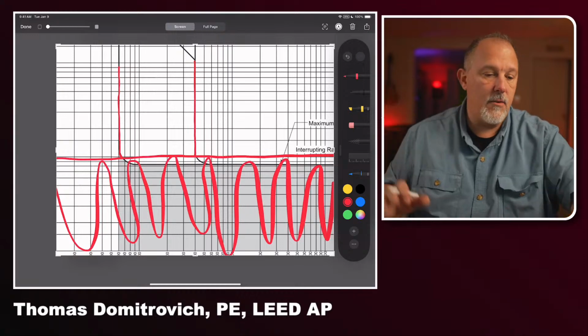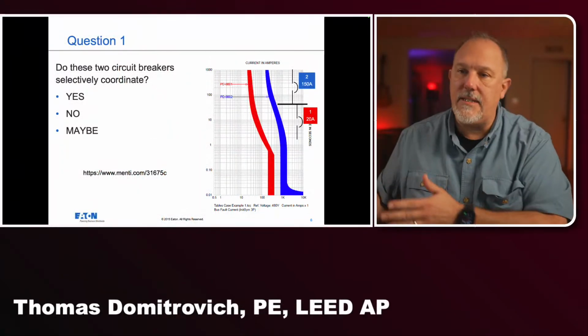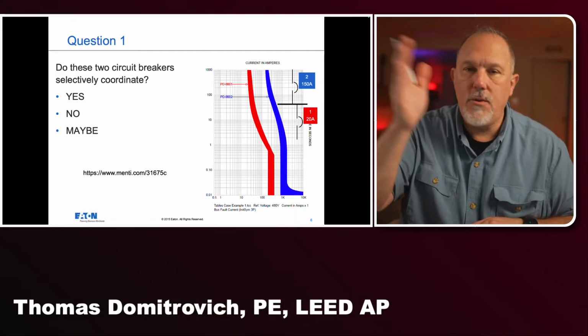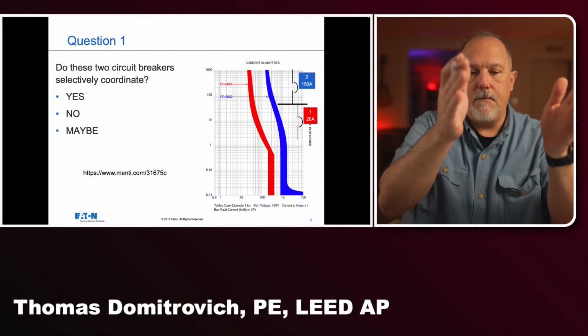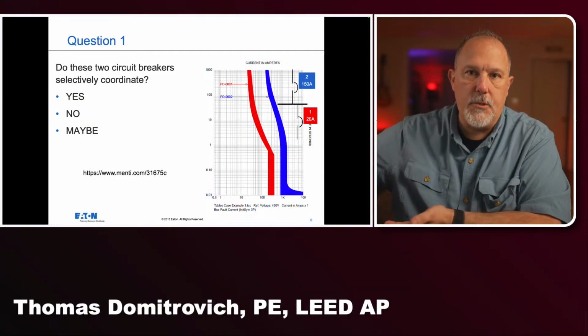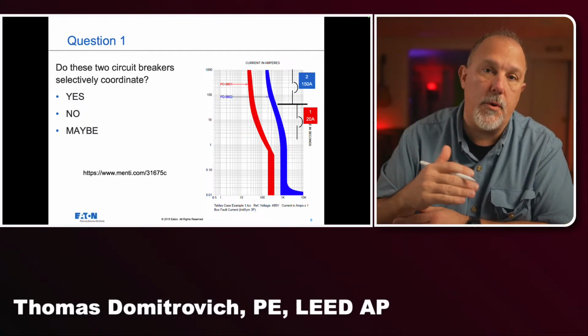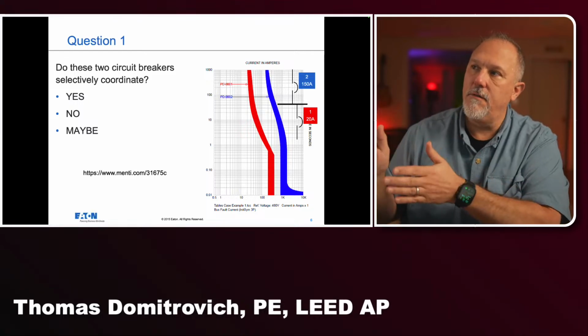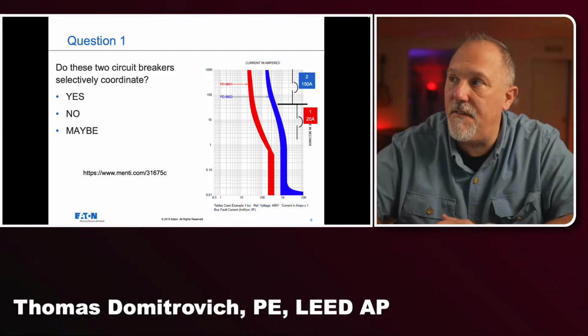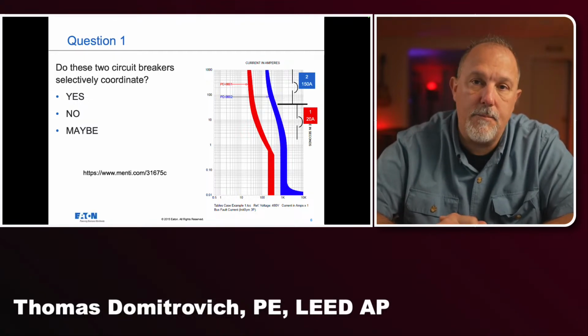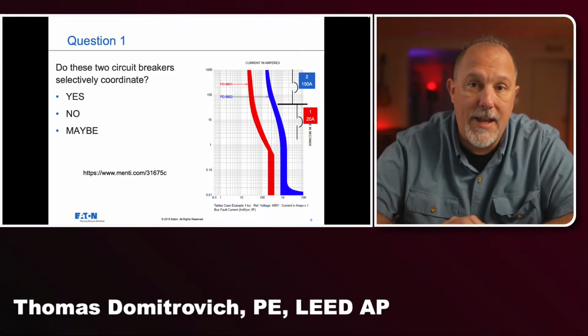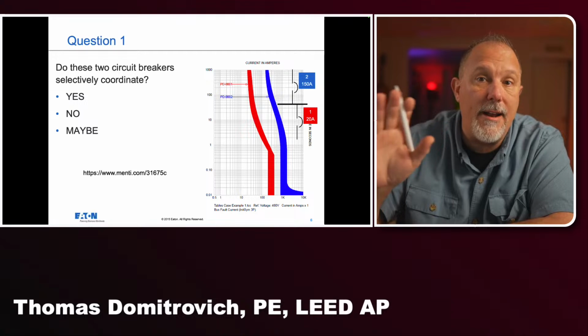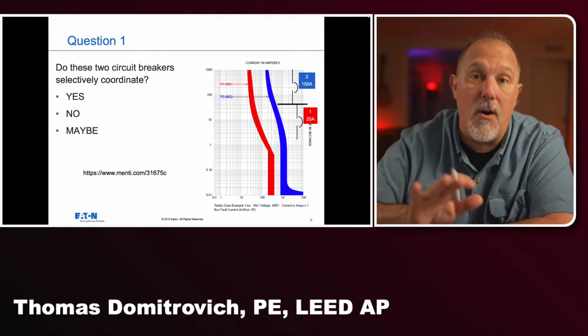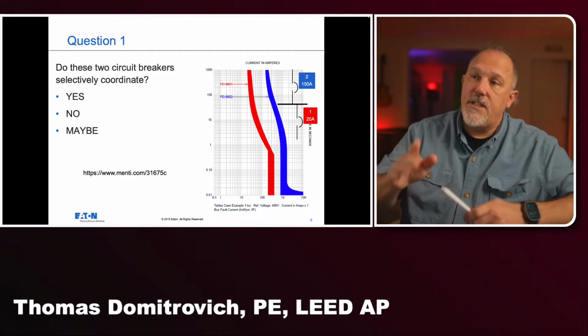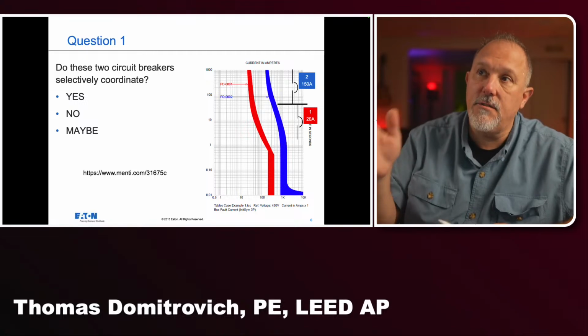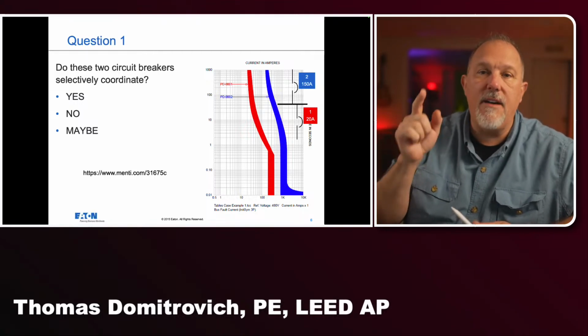So you don't see it when you plot, when you go to SKM, Easy Power, EDSA, whatever. You don't see the instantaneous boot, so to speak, region because it is below 0.01 seconds. So in this trip curve, I am not cutting off the curve at the fault current for the 20 amp breaker. That is the 20 amp breaker. In fact, I'm not plotting available fault current on this slide at all, which is why the answer to this question is maybe, because you don't have enough information.